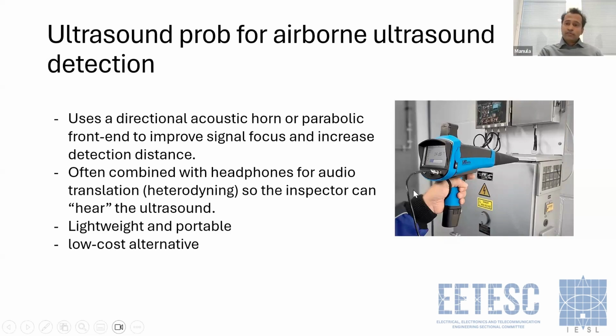On the other hand, often with these devices, the manufacturers provide a headphone. Of course, we can't hear ultrasound, but this device can convert the ultrasound into lower frequencies so that users can hear it. Based on this hearing perception, the intensity of the sound, they can get a clue about whether there is a strong ultrasound presence, for example, inside this high voltage cabinet. In that way, we can measure faults like partial discharge. This is a lightweight and portable device, and it is a low cost alternative as well.